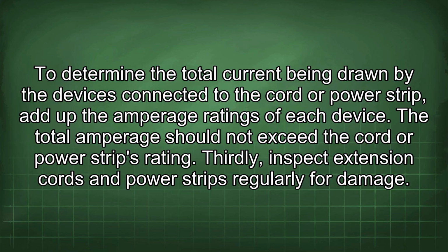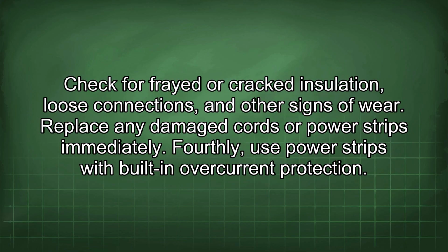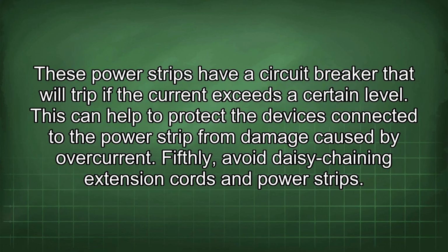Thirdly, inspect extension cords and power strips regularly for damage. Check for frayed or cracked insulation, loose connections, and other signs of wear. Replace any damaged cords or power strips immediately. Fourthly, use power strips with built-in overcurrent protection. These power strips have a circuit breaker that will trip if the current exceeds a certain level. This can help to protect the devices connected to the power strip from damage caused by overcurrent.